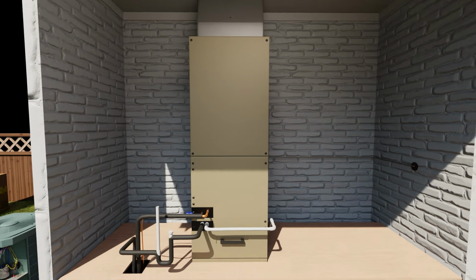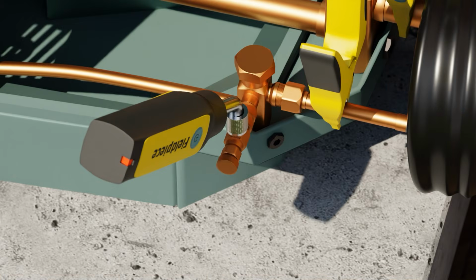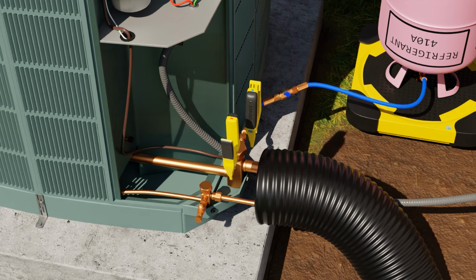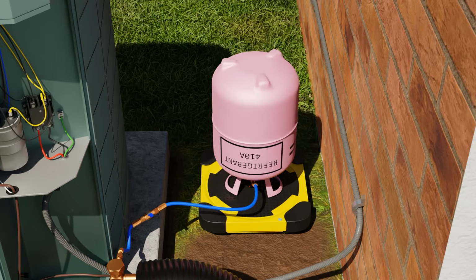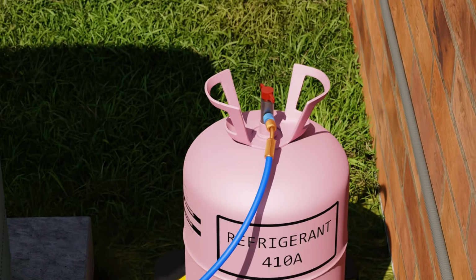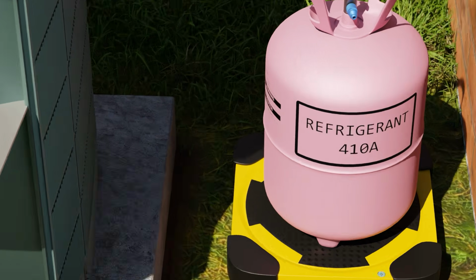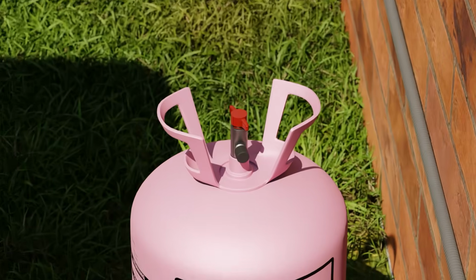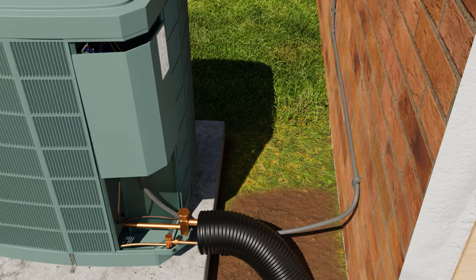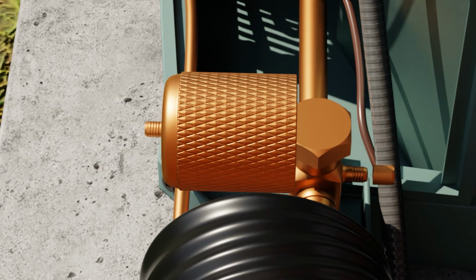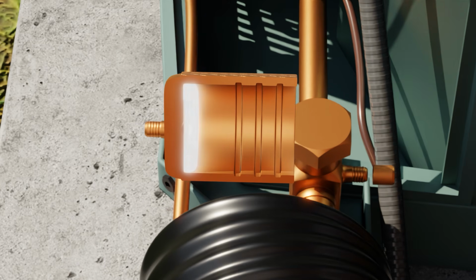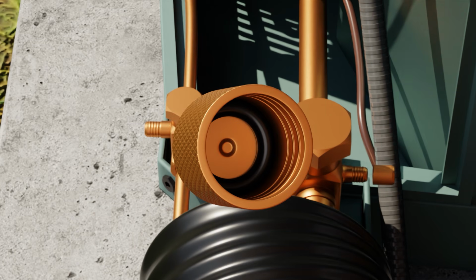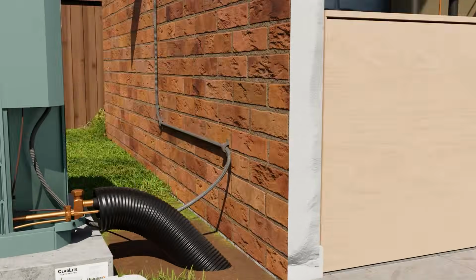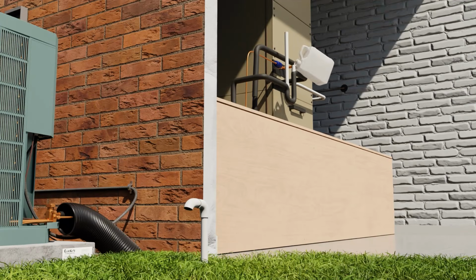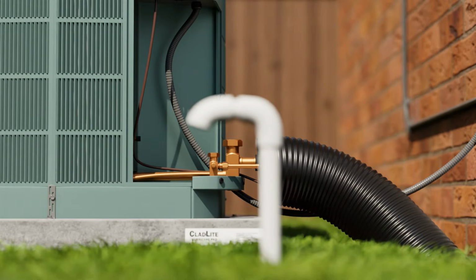Once you've done all your tests and you've ensured that the system is performing properly, you can go ahead and reverse the process. Remove all your ports and probes and reassemble the system completely, making sure you clean up everything. Before putting caps back on, make sure the rubber seal is still in the caps. Finally, test the drain. Make sure it drains properly by filling the trap, and when it's running, make sure the condensate drain is draining if you're running in cooling mode.